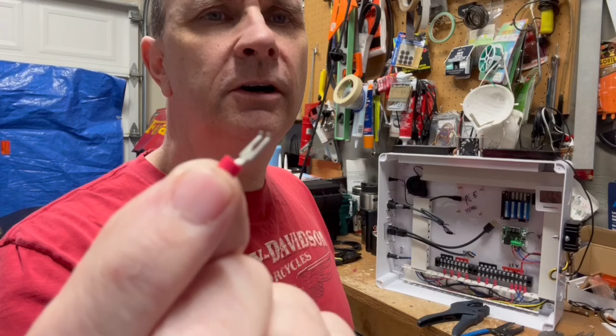I tried to use those, but ended up using these instead because the terminal strip I installed in the enclosure was too small for the eyes I had. Notice these forks have a little hook on the end. Normally I don't use forks because they can pull off or get loose, but these have a hook that goes underneath the screw so they can't pull off. Those are really good ones.